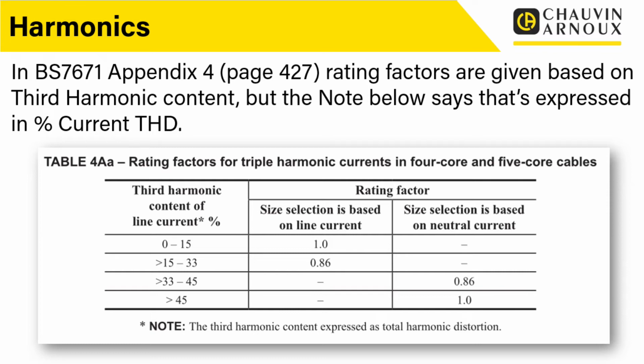So when I read this originally, it did look a little bit like double counting. It looked like they're applying a factor to it and then applying a factor again. But I think what we're doing is correcting the design current based on the overall harmonic content using THD. And then we're looking at the effects of triplen harmonics, but they're also using THD as the dividing line for the triplen harmonics as well.